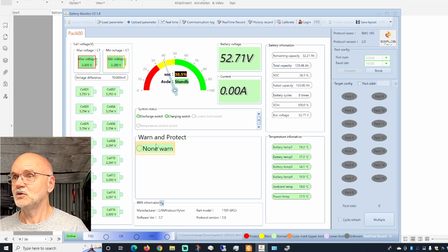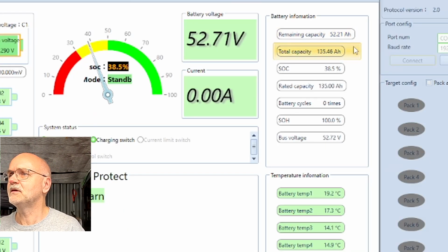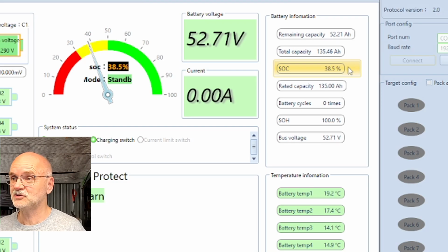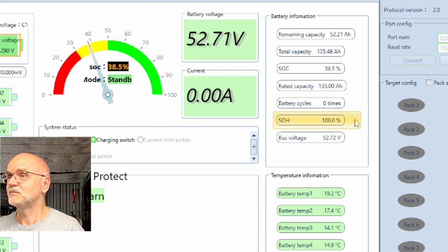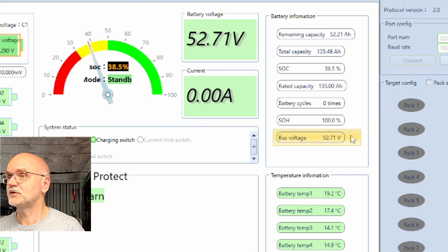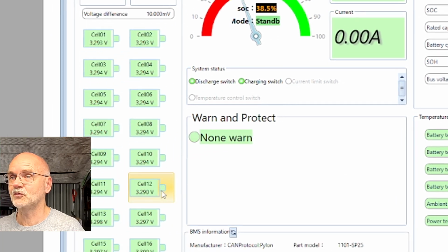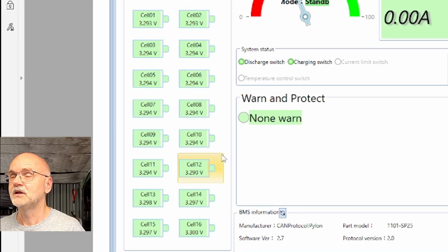So, no warning. Remaining capacity, total capacity 135. We are at 38.5%, which could actually be true. Rated capacity, cycles, nothing. SOH, 100. Bus voltage, 52. Temperatures. This all seems to work. We've got all the cell voltages here.